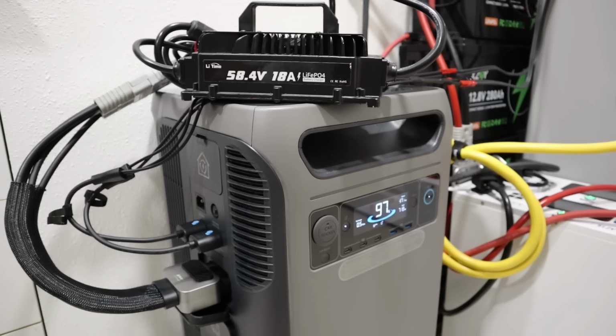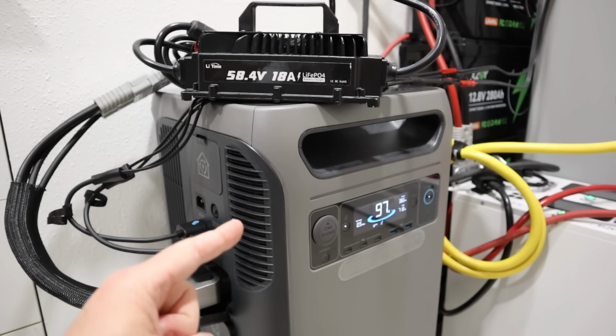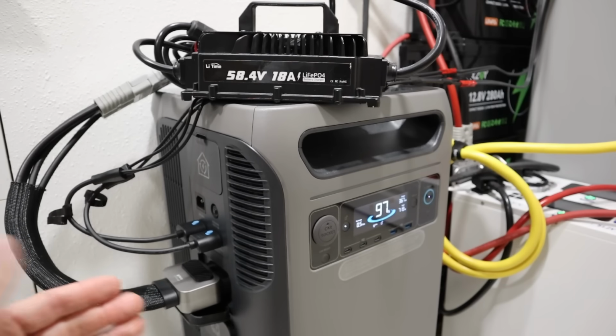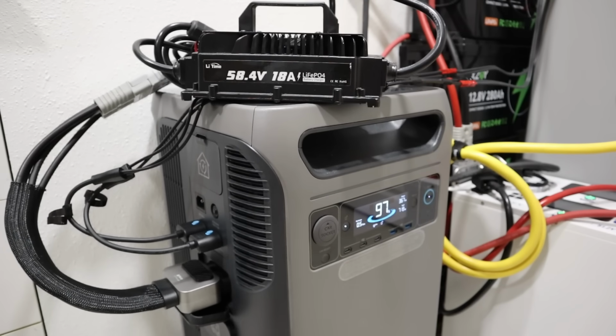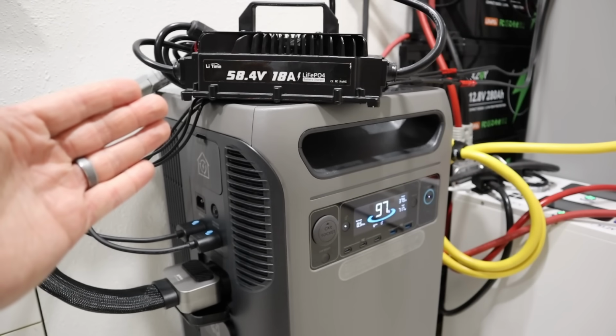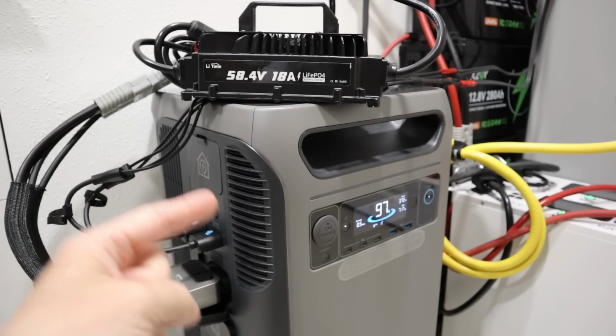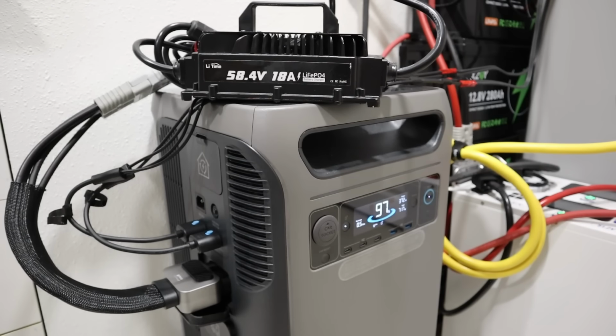Well, as everything was getting up to 100% state of charge, in fact, the power station had been at 100% state of charge for a bit of time, but these batteries back here weren't quite there. After it got above 58 volts, the inverter shut off for the power station. So if you go above 58 volts, there's a chance that this will shut off from high voltage.